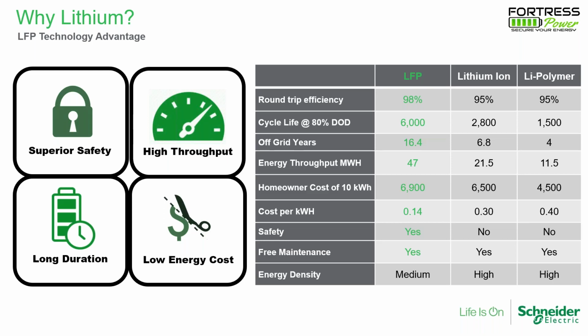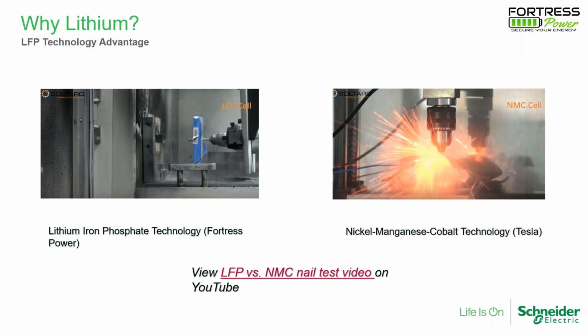Next slide, please, Jeremy. Here's a simple test between the lithium iron phosphate and the NMC cell. That's the penetration test. On the left side, you see slight smoke come out, but there's no fire. With NMC, as soon as it starts to penetrate the whole system, it catches fire. Although it has high energy density and is very popular in the automotive industry, in the energy storage sector we don't worry too much about space. We're already much smaller than traditional lead acid. So that's one of the deciding factors for us to choose lithium iron phosphate. Next slide, please.